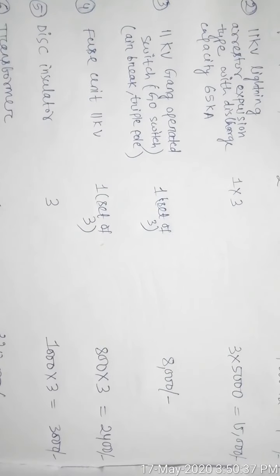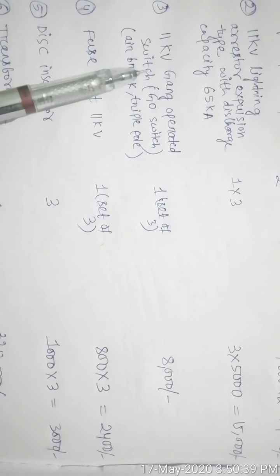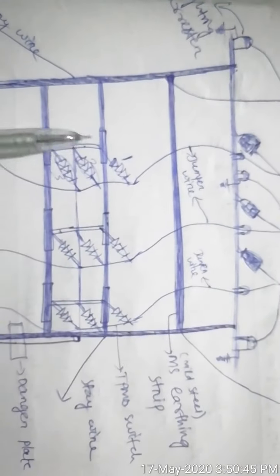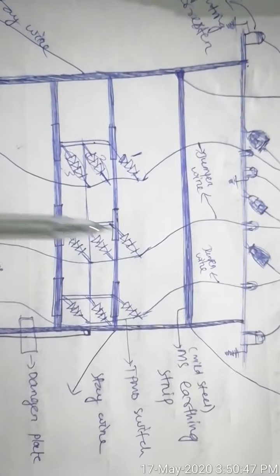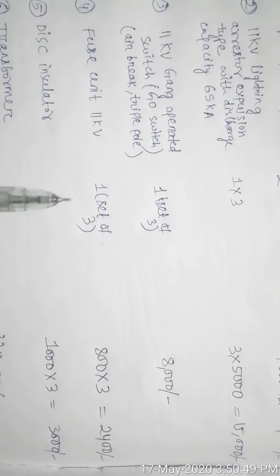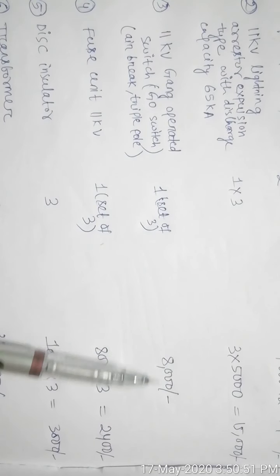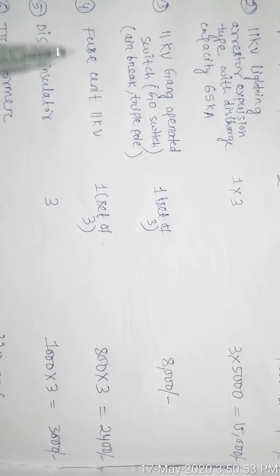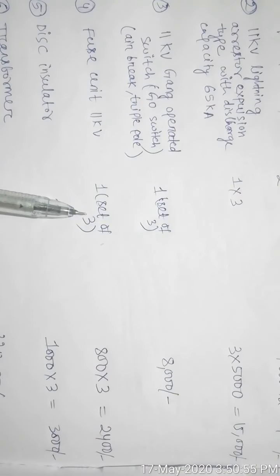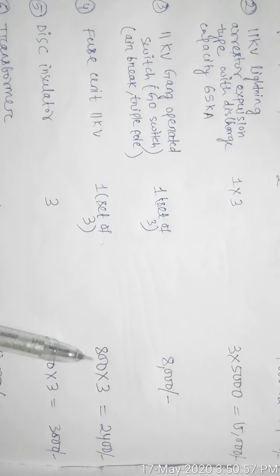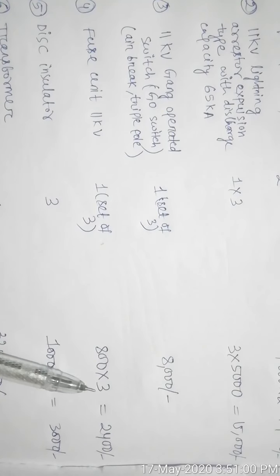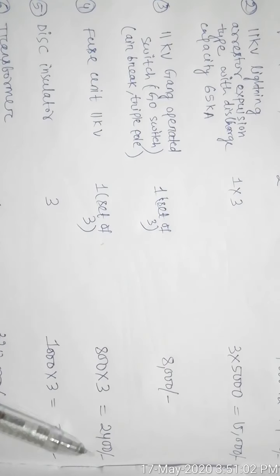The third part is an 11 kV gang operated switch. The gang operated switch is placed just below the lightning arrestor, and it costs approximately 8,000. The next is the fuse unit. Fuse unit cost is 800, and as there are 3 units, we require to invest 2,400.